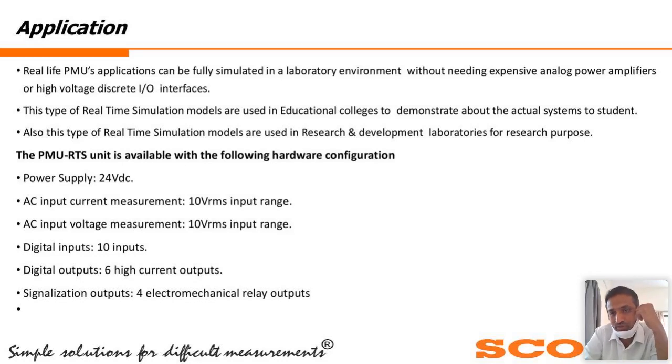Okay, Mr. Manoj asked one question. What phasor estimation algorithm does the PMU use? Is it DFT? Yes, mostly DFT or Visimax. In the Visimax case, they use their own patented algorithm. So you have a choice of using the patented Visimax-owned algorithm or the general DFT algorithm. You can choose it in the PMU itself. If you want to use both, it will run both in parallel and give the output based on the first decision. Otherwise, you can select only DFT and use DFT.